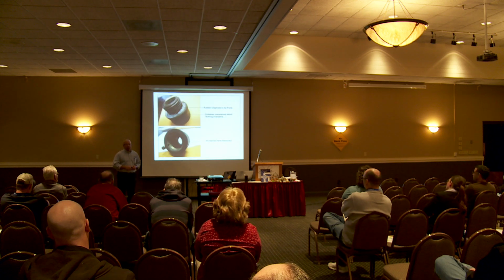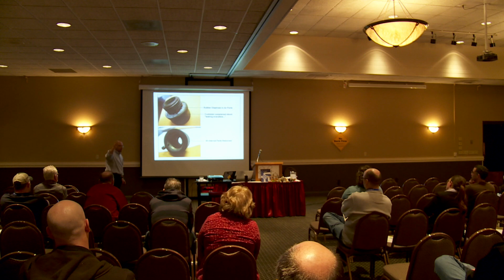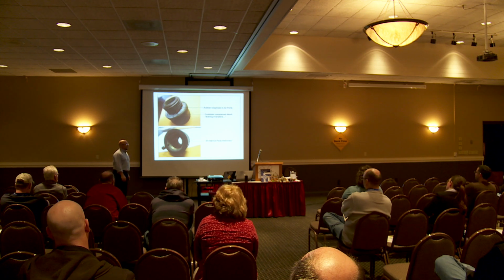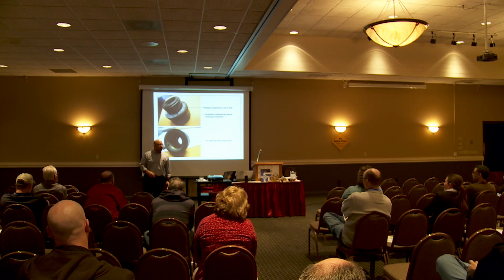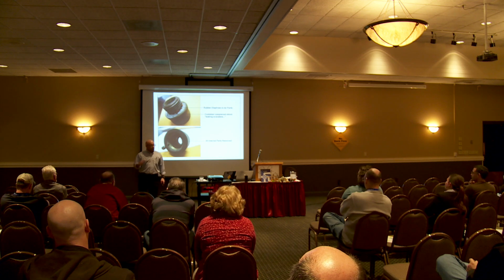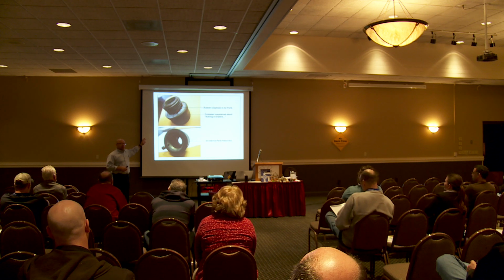How about this one? One of our other surveyors, Rick Kinney, found this one. This is a thread-on vacuum breaker, like on our home spigots and whatnot. And so Rick's there doing the survey, and the guy walking along with him said, "Oh, I fixed that darn thing. It was leaking all over the place." Red flag for Rick. Now this, again, is a compliant backflow preventer. I should say it was. Okay? From 5 feet away, it looked perfectly fine.